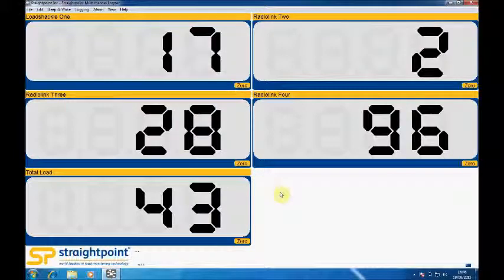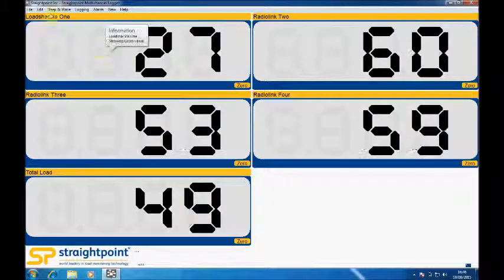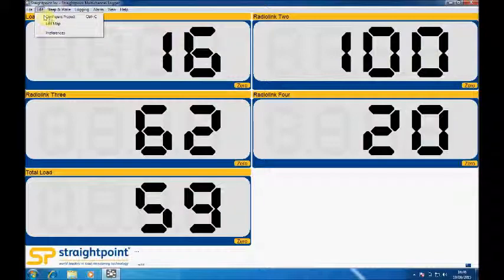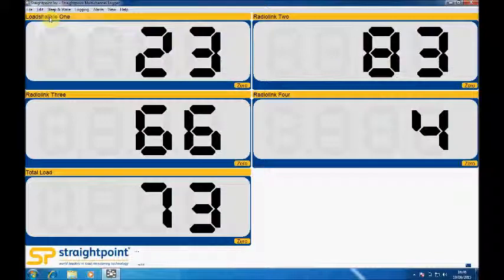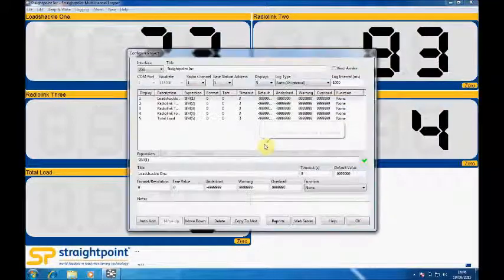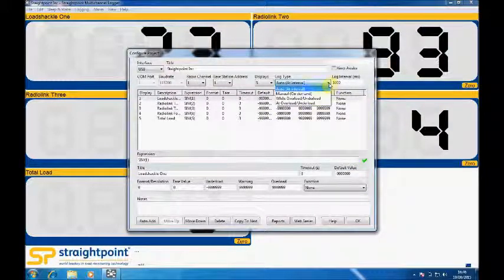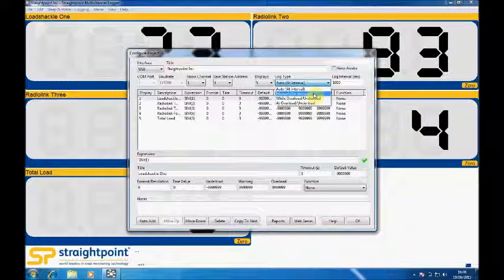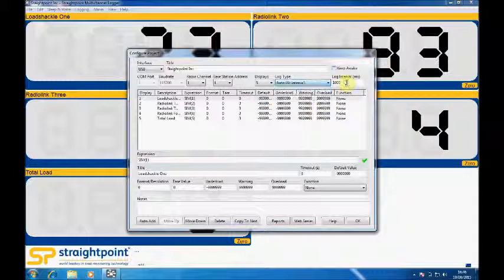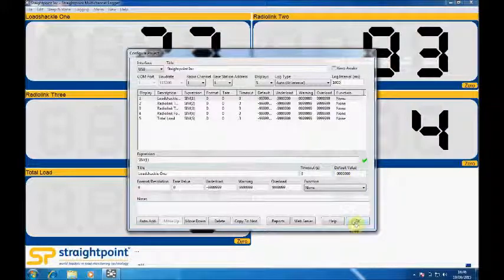If you want to data log the data for your lift per load cell it's quite simple to do. You come to configure project and from here you can set the software to log automatically at a set interval or manual so you press start and stop, or while an overload or under load condition. This is useful if you don't want to gather data below or above a certain reading. This here allows you to change the interval for logging. We'll leave it set at 1000 milliseconds.